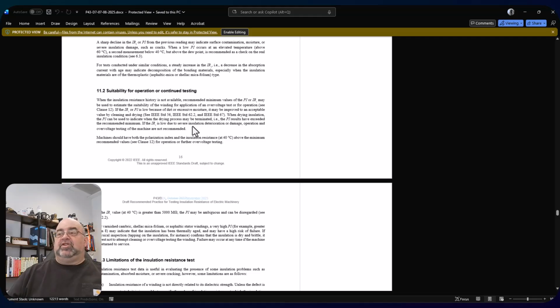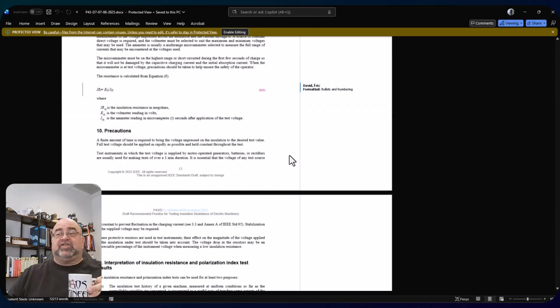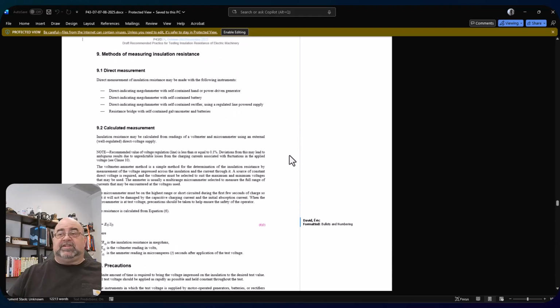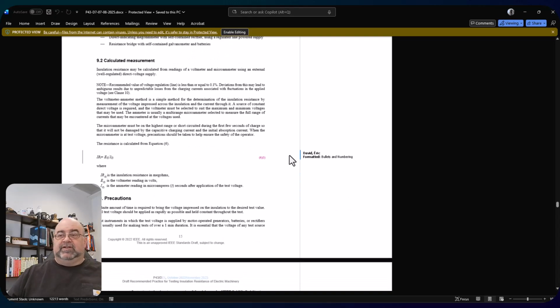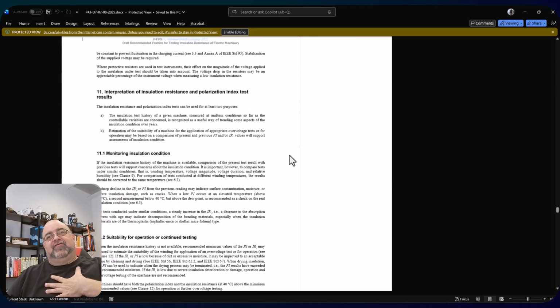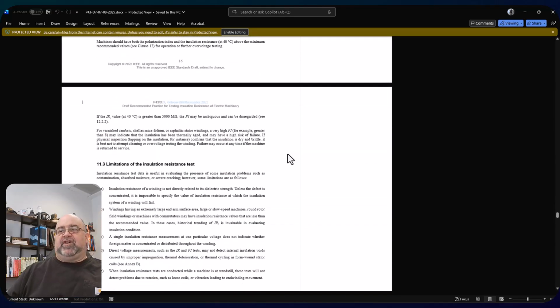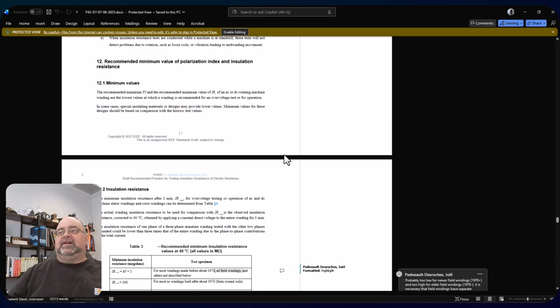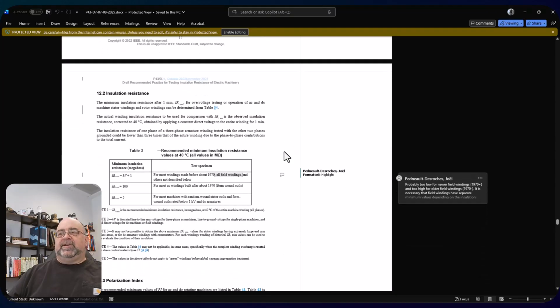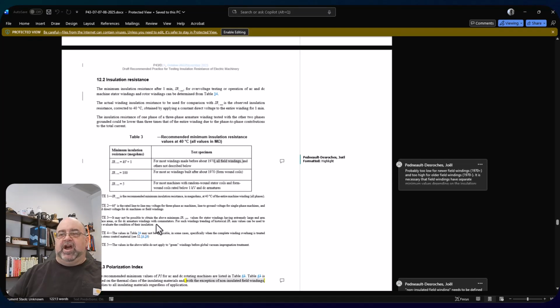If the IR is low due to severe insulation deterioration or damage, operation and overvoltage testing of the machine are not recommended. So if I have a low insulation resistance, I just don't perform the high voltage test. And in all of your automatic tests, that's what happens. It comes up, it goes click, turns off. Mind you, I do force them sometimes just for fun to see the little lights. Insulation resistance. Okay, here we are.